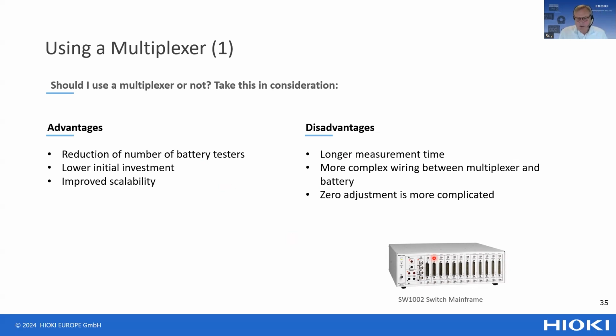On the other hand, using a multiplexer will result in a longer testing time than when you do all the battery measurements simultaneously in parallel. Also, the wiring between the multiplexer and the batteries is more complex, and performing zero adjustment of a system using a multiplexer is a lot more challenging than just doing zero adjustment on a direct connection between the battery tester and the probe. So depending on the circumstances, you have to decide if you want to use a multiplexer or not.